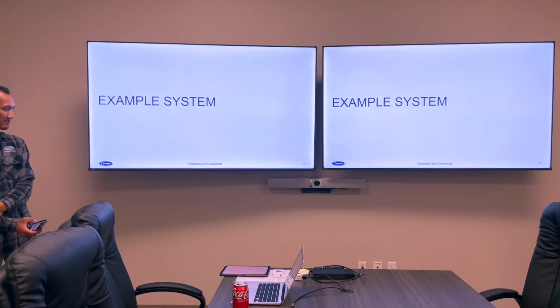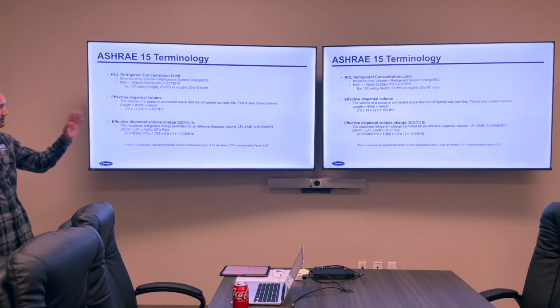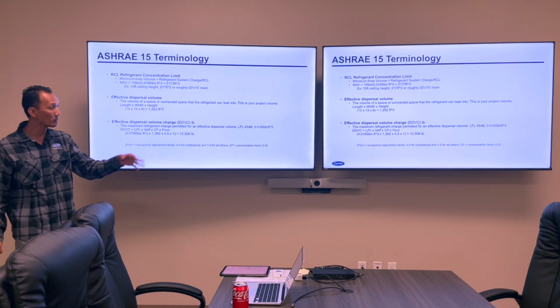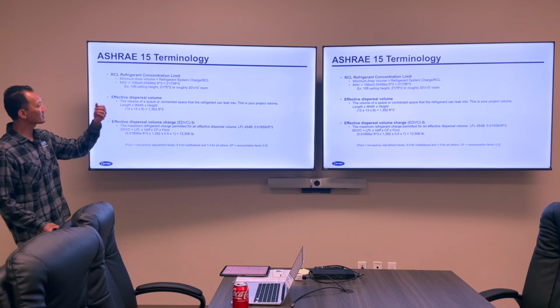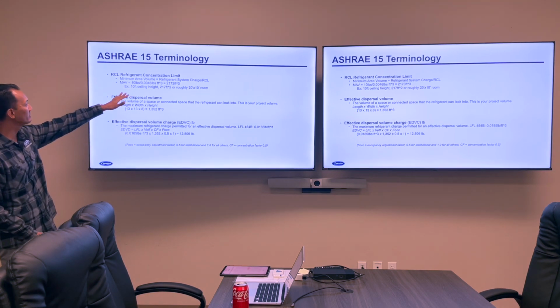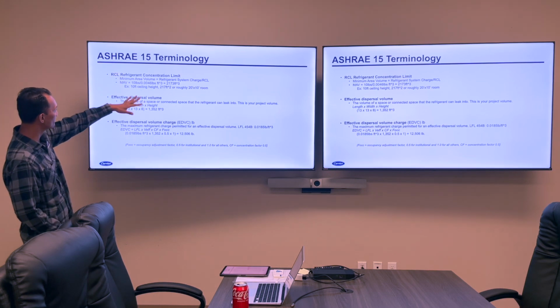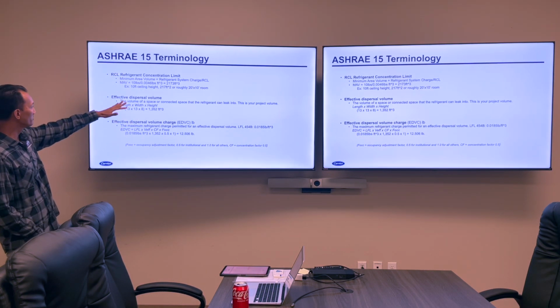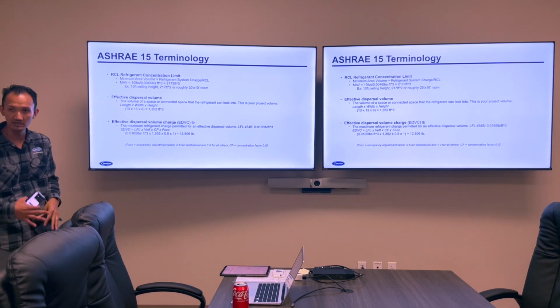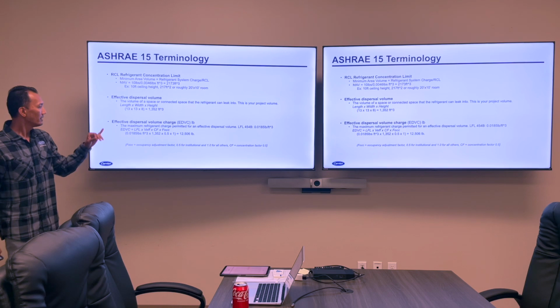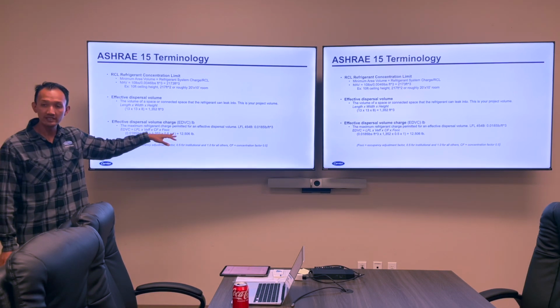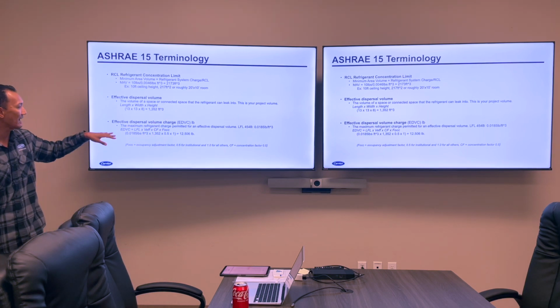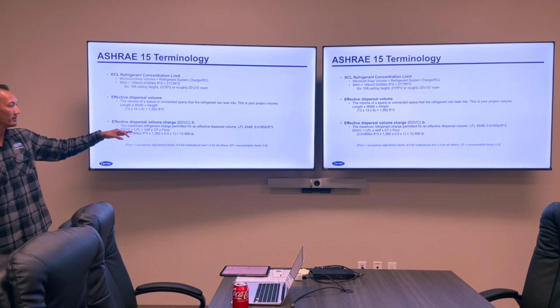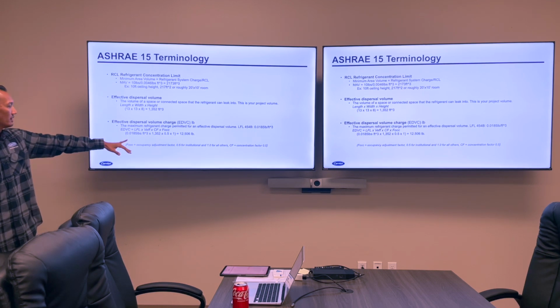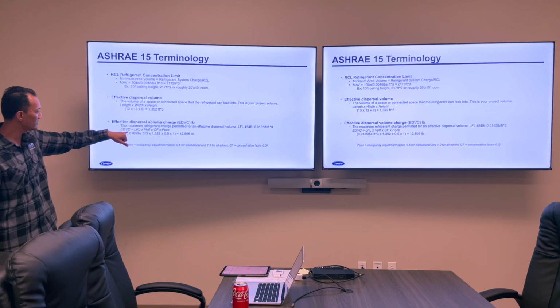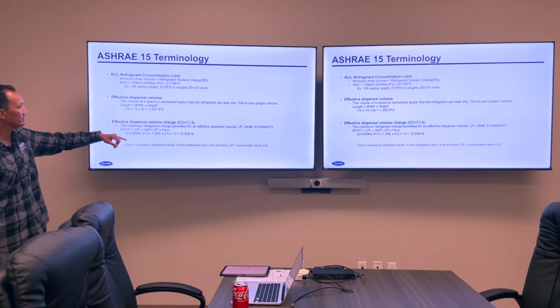Yeah, so we have a simple example system that we want to go over, but before we go over that, just to get some terminology out of the way so we know what we're talking about. RCL, we talked about a little bit. It's the refrigerant concentration limit. We use that to calculate our minimum area. Volume: effective dispersal volume, that's basically length times width times height. Effective dispersal volume charge, or EDVC, this is the formula that helps us calculate the maximum refrigerant charge permitted for a given volume. So the equation is EDVC equals LFL, which we can get from those ASHRAE tables.